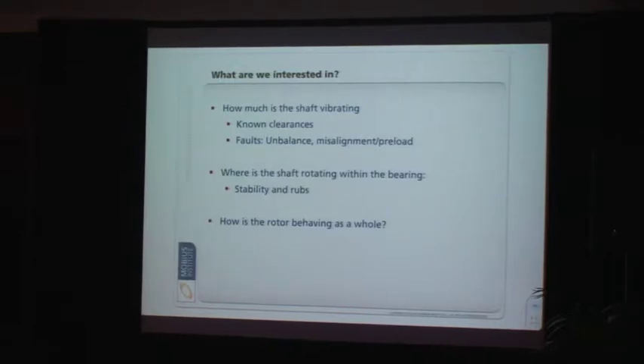Of course, you can just put the sensors on and look at it from a protection point of view. For the amplitudes, which in this case is literal displacement of that shaft within the bearing, if we see it exceed a certain level, we have to shut down because it's exceeding those thresholds. But we would also like diagnostic information so we can tell exactly what's going on, whether it's a design issue, maintenance issue, or even a process issue.